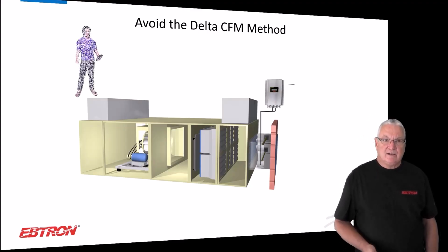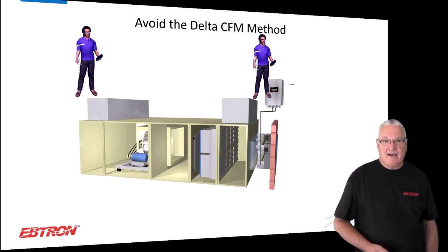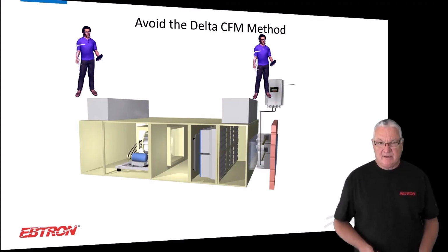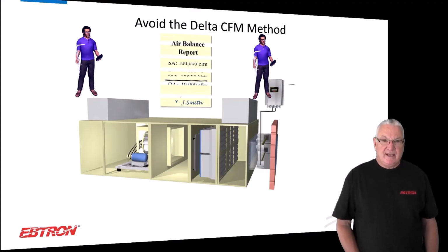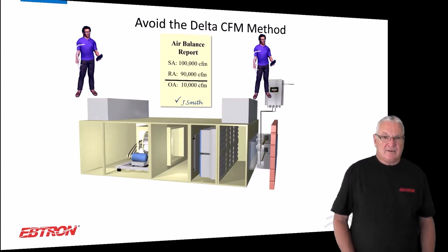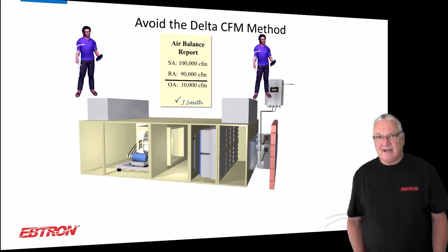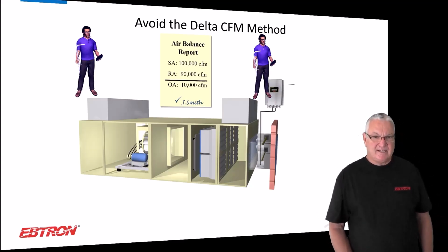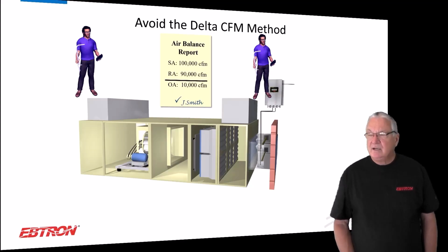And so here I'm going to say, again, I'm going to measure the supply and the return. I'm showing an air balance doing it, but it could have been permanently mounted devices. You measured 100,000 on the supply and 90,000 on the return, so you said you got 10,000 CFM of outside air. It's like, okay, but what's the uncertainty of those measurements? And like I said, it's going to run 3 to 10%.